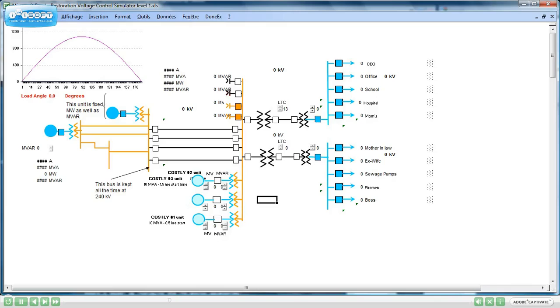The users have to energize all the lines and pick up all the feeders with cold load characteristics, while keeping the voltage within very close limits, at all times and at every location. The users also have to take care of ferroresonance effect. Ferroresonance will take place when there are 2 transformers in series with no load. Let's go for an example.